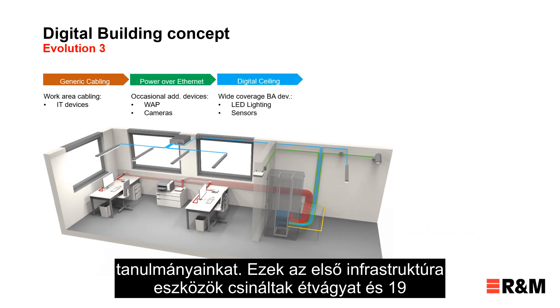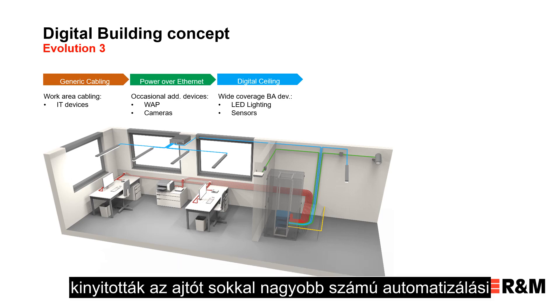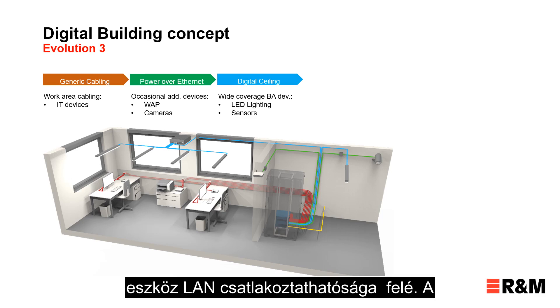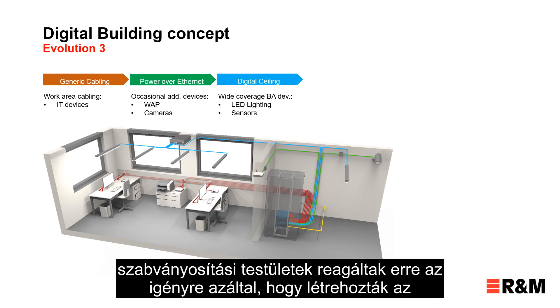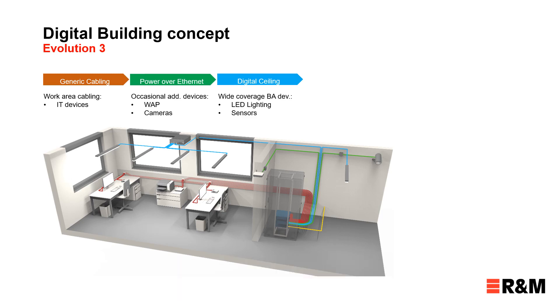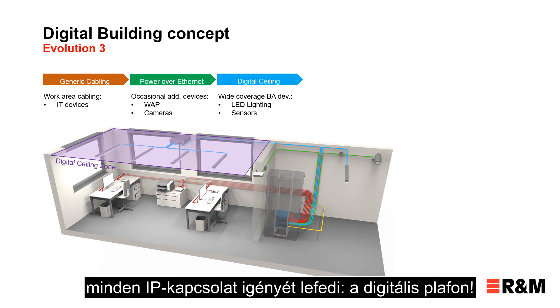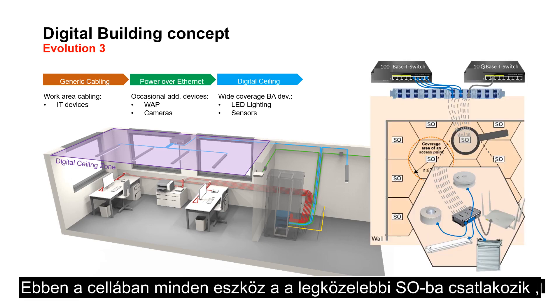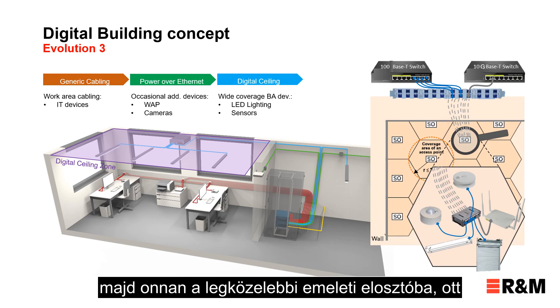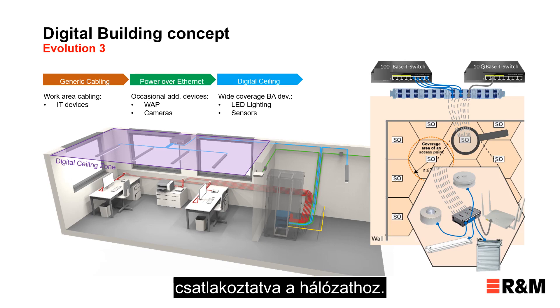These first infrastructure devices opened the door for many more building automation devices to be connected to the LAN. The standardization committees reacted to this demand by creating the ISO IEC 11801-6 standard, which specifies structured cabling in the ceiling with a service outlet covering a predefined zone for all-IP connection needs — the digital ceiling. All devices in this zone connect to the nearest service outlet and from there to the nearest floor distributor.